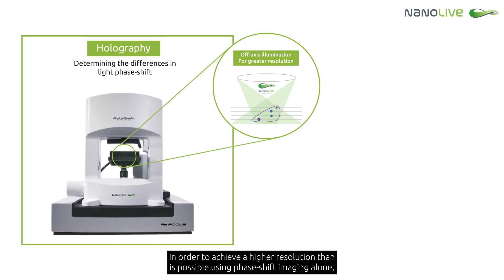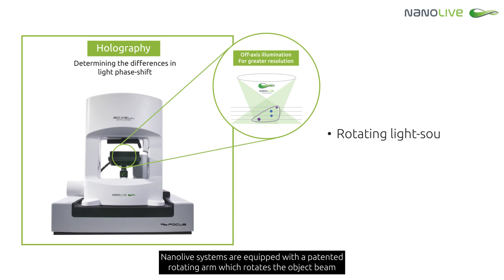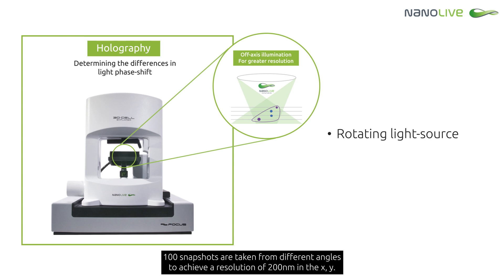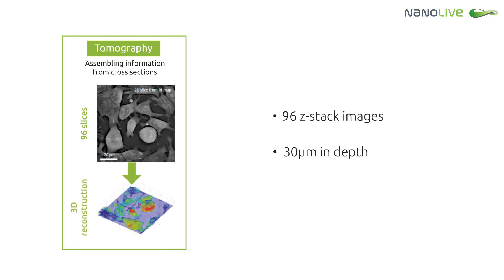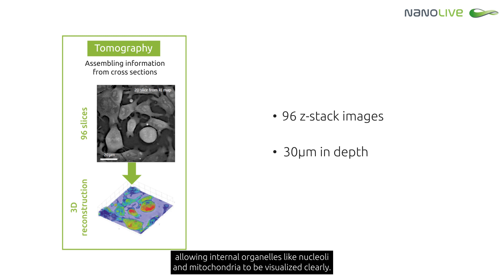In order to achieve a higher resolution than is possible using phase shift imaging alone, Nanolive systems are equipped with a patented rotating arm which rotates the object beam 360 degrees around the sample. 100 snapshots are taken from different angles to achieve a resolution of 200 nanometers in the XY. 96 2D image slices are taken in the Z-stack covering 30 microns in depth, allowing internal organelles like nucleoli and mitochondria to be visualized clearly.